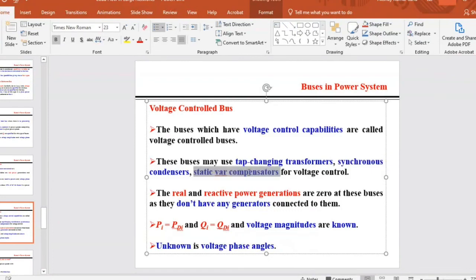We also use something called a static VAR compensator, which compensates the reactive power, bringing the voltage level of those respective buses to a value where the system is stable. We use different types of equipment depending on where it is, how efficient it needs to be, how much money we can spend, and other factors.